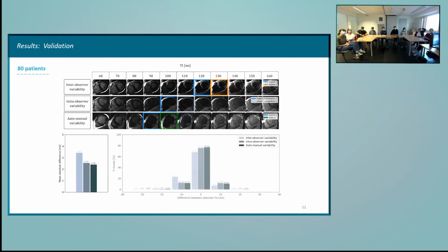It doesn't matter, because you don't care about the real T1. You just want to have the background nulled. Yeah, but since you modify the magnetization, the recovery won't follow the T1 recovery curve because you are hitting it every single time to get your Scout images. You're measuring an apparent T1 recovery. You don't measure T1.